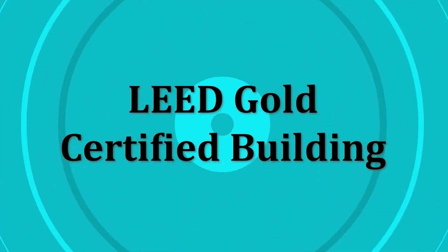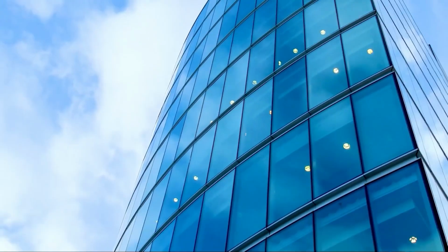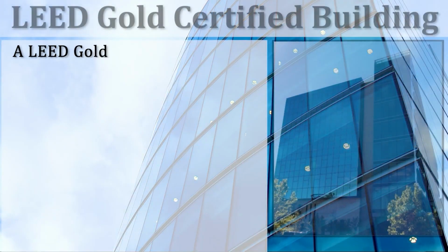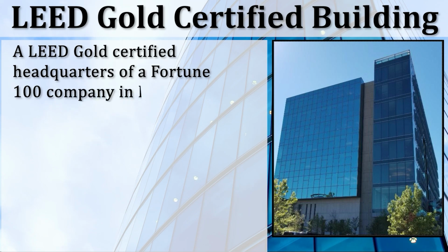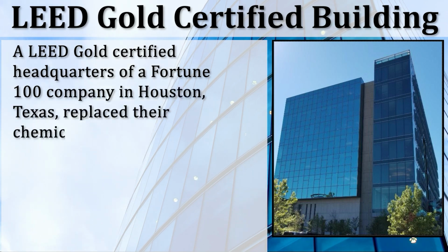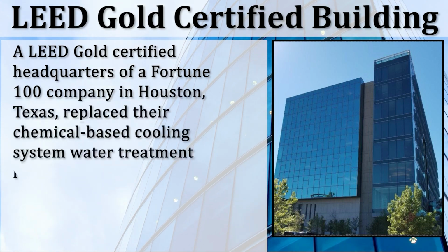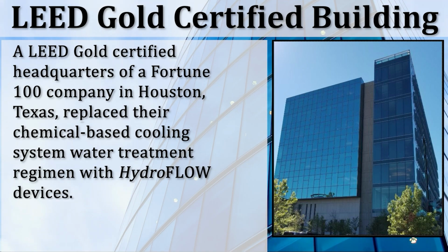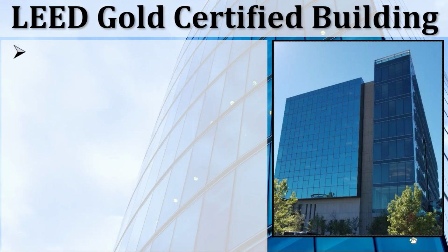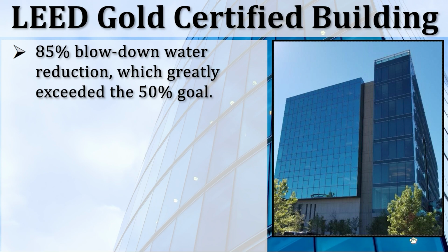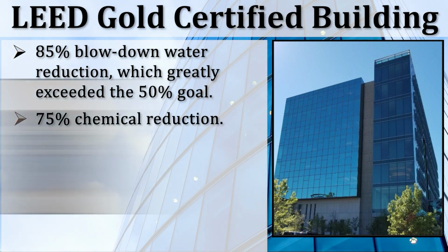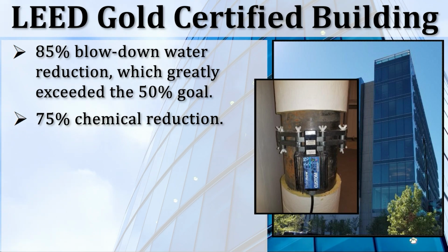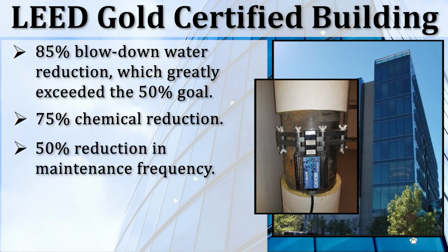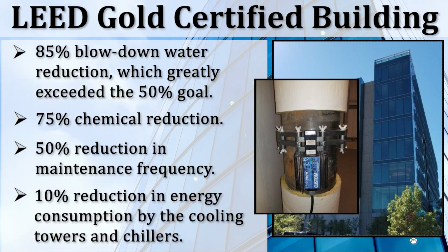LEED Gold certified building. A LEED Gold certified headquarters of a Fortune 100 company in Houston, Texas, replaced their chemical-based cooling system water treatment regimen with HydroFLOW devices. Results: 85% blowdown water reduction, which greatly exceeded the 50% goal, 75% chemical reduction, 50% reduction in maintenance frequency, and 10% reduction in energy consumption by the cooling towers and chillers.